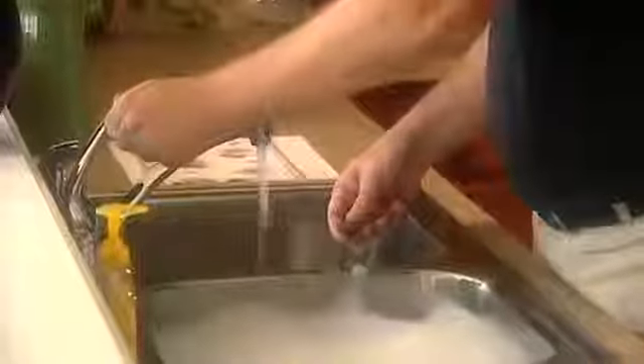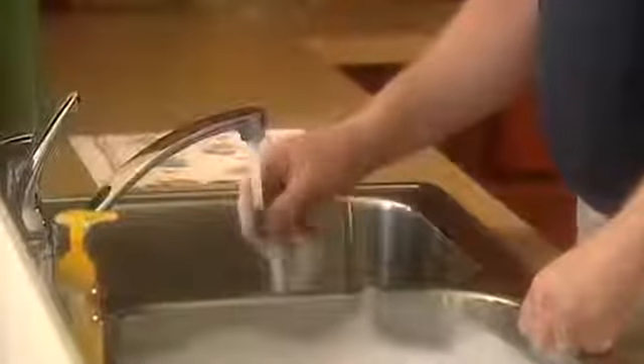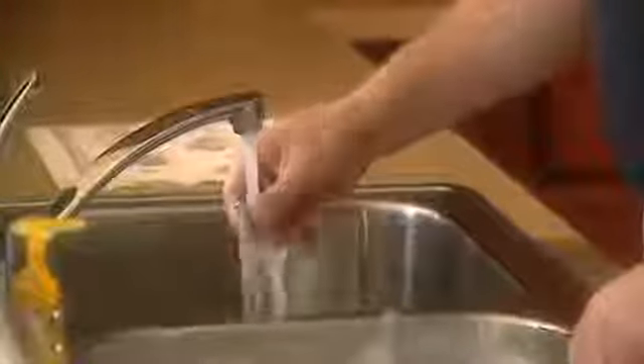Your DeVilbiss CPAP device has been designed for years of worry-free operation when properly maintained. The air inlet filter should be checked every 10 days and cleaned if necessary. Simply remove the dark outer foam filter from its frame and wash in a solution of dishwashing detergent and warm water. Allow the filter to completely dry before reinstalling. If the filter becomes damaged, contact your home care provider for a replacement. If an optional fine particle filter has been installed behind the standard filter, check for dirt or damage every 10 days and replace if necessary. Regardless, the fine particle filter should be replaced every 30 days.